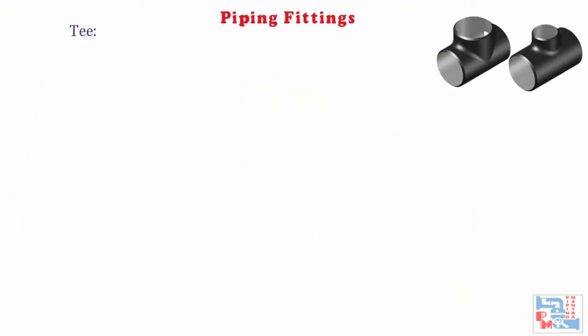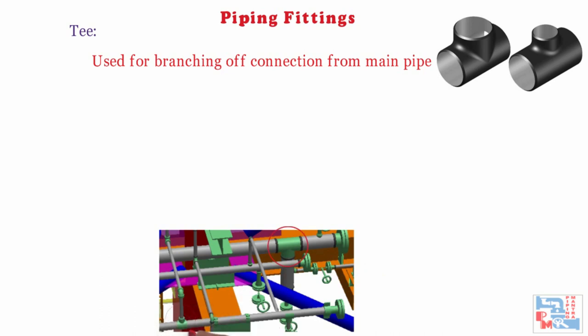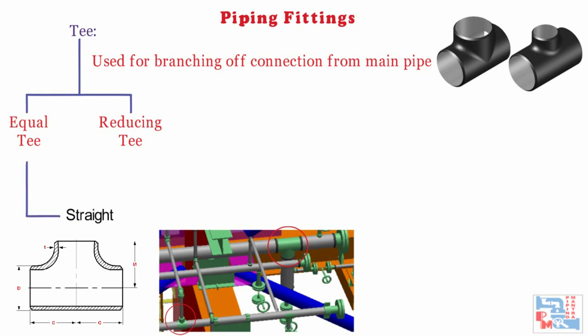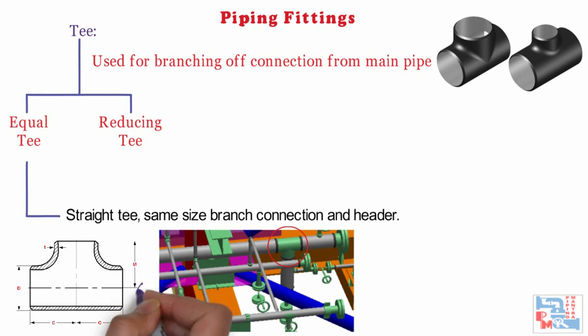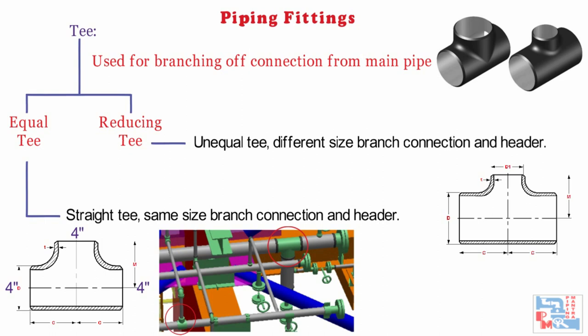Tees are used for branching of connection from the main pipe. There are two types: equal T and reducing T. Equal T, also known as straight T, is used to have a same-size branch connection as the header — all three ports have the same size connection. Reducing T, also called unequal T, is used to have a different (smaller) size branch connection from the header. For example, two header ports may have 4-inch connections while the branch has a 2-inch connection.